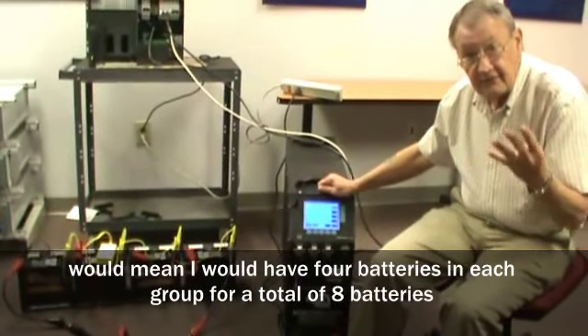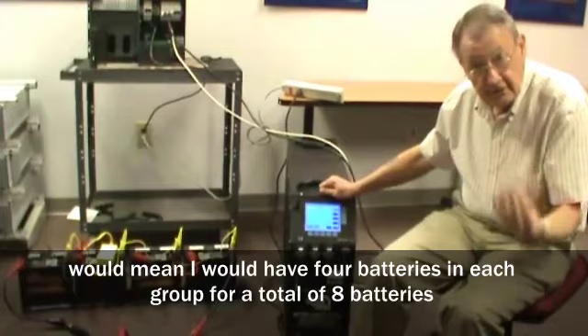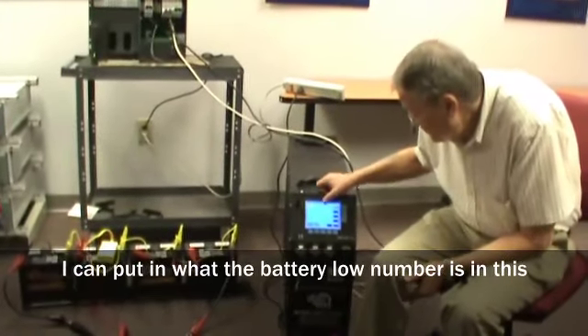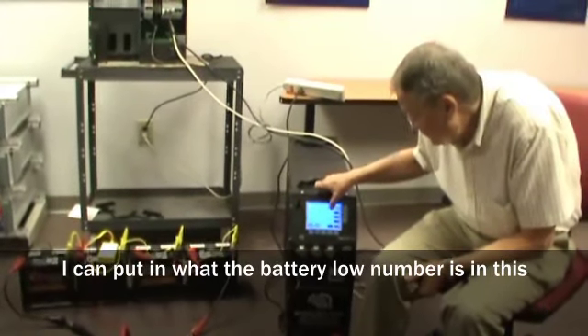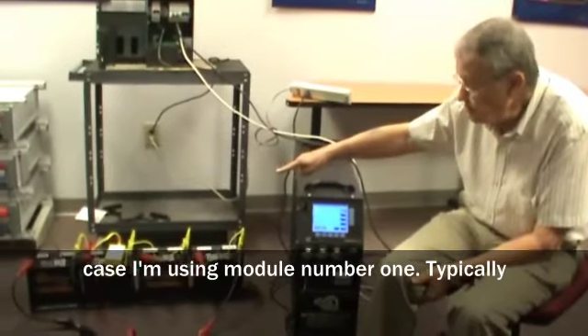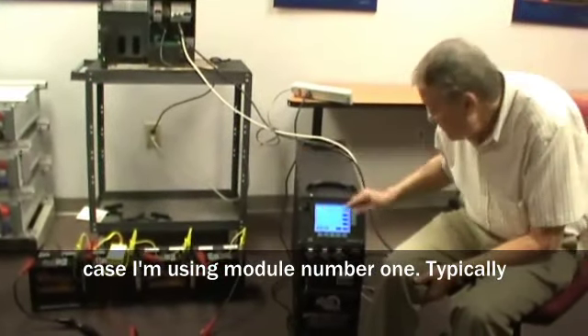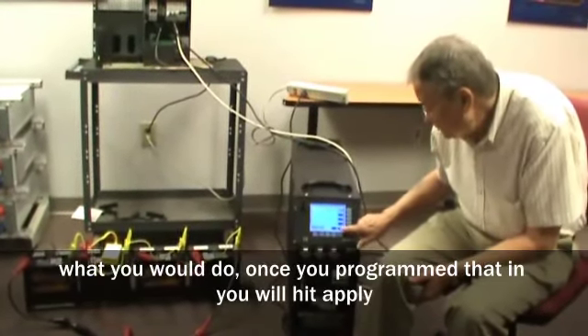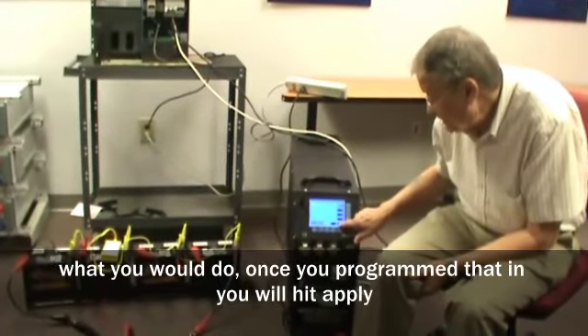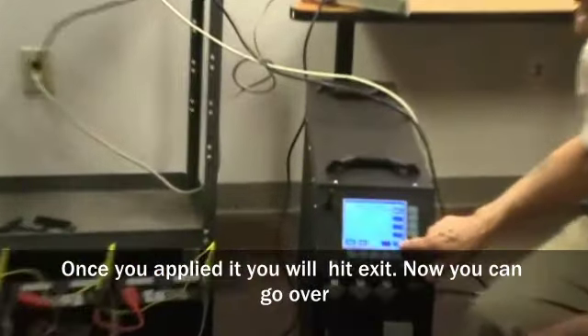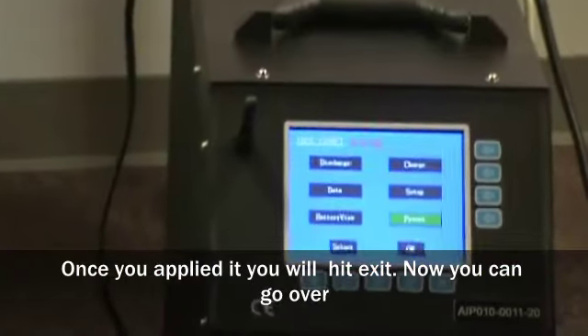So that means I would have 4 batteries in each group, or a total of 8 batteries. I can put in what the battery low number is. In this case, I'm using module number 1. Okay. Then typically what you would do, once you program that in, you would hit apply. Once you've applied it, you would hit exit.